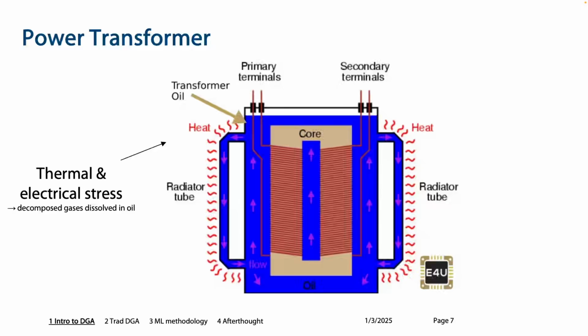Electrical stress, if there's any electrical fault, like a sparking or partial discharge, will try to release a bunch of strong electrical energy into the oil and break down the oil into some gases. That's what we call decomposed gases in the oil, and these gases will dissolve into the oil, hence the name dissolved gas.